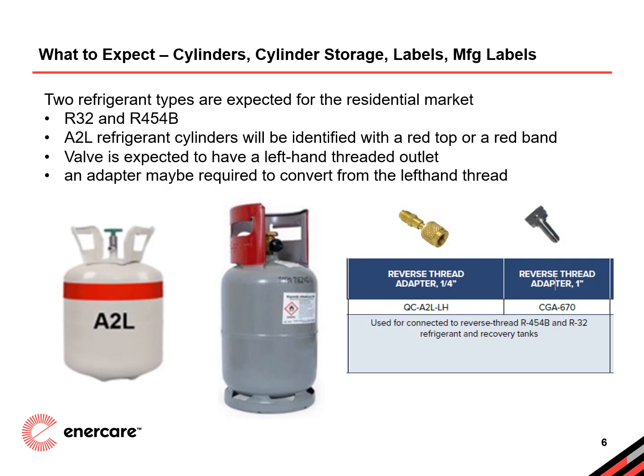Continuing deeper into what you can expect with A2Ls in the residential market, the two refrigerants that are likely to dominate, R32 and R454B, will be clearly marked for identification. Look for cylinders with a red top or red band to signal that they contain A2L refrigerants. Now, there's an important technical detail to be aware of here.